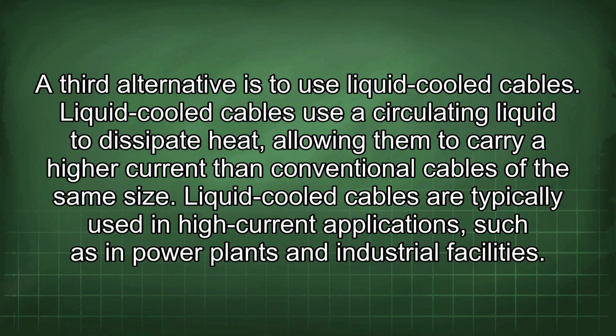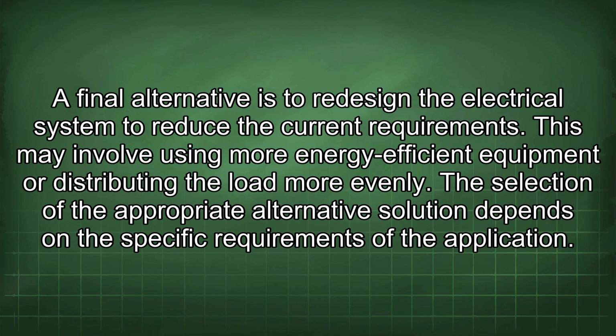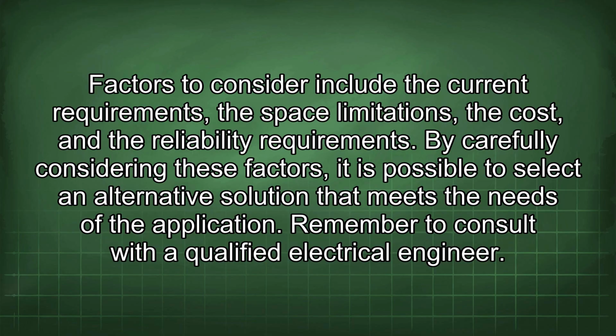A third alternative is to use liquid-cooled cables. Liquid-cooled cables use a circulating liquid to dissipate heat, allowing them to carry a higher current than conventional cables of the same size. Liquid-cooled cables are typically used in high-current applications, such as in power plants and industrial facilities. A final alternative is to redesign the electrical system to reduce the current requirements. This may involve using more energy-efficient equipment or distributing the load more evenly. The selection of the appropriate alternative solution depends on the specific requirements of the application. Factors to consider include the current requirements, the space limitations, the cost, and the reliability requirement. By carefully considering these factors, it is possible to select an alternative solution that meets the needs of the application.